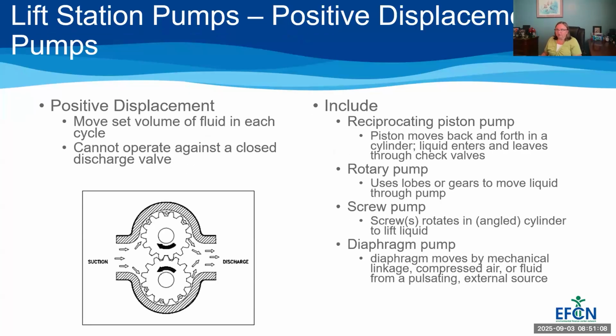So we're going to look at the positive displacement pumps just real quick so that you're familiar with them. Again, they move a set volume of fluid in each cycle, so it's constant flow rate, but they cannot operate against a closed discharge valve. So different types of pumps mentioned here. I said a screw pump. You're probably familiar with a diaphragm pump if you've ever had a chemical metering pump. A rotary pump is what's shown in this picture, where you've got gears moving liquid through the pump, and then a piston. You guys are probably familiar with pistons, but they're like pushing water, and then the check valve closes and the piston goes back and the check valve opens and it pushes water. So that's a piston type pump. So those are all positive displacement type pumps, and you should be familiar with them.